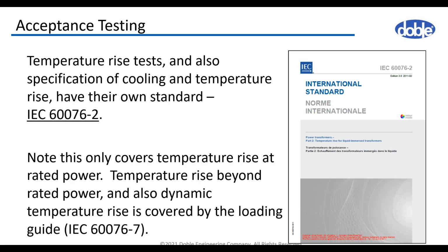Some of the tests have their own standards, and that's the case with the temperature rise test, which, along with the specification of cooling and temperature rise, is described in another standard, which is IEC 76 Part 2. It covers the test at rated power, and if we need to perform the test at some power mode beyond the rated one, or let's say dynamic temperature rise, we should refer to the loading guide, which is a separate standard, IEC 76 Part 7.